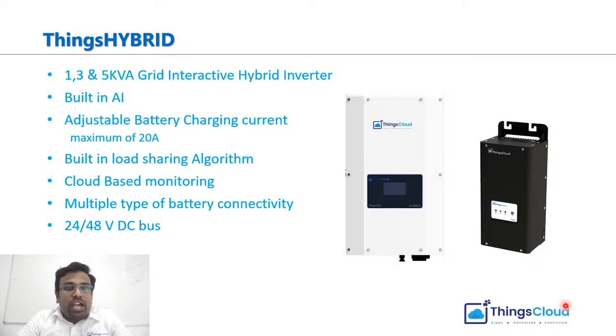And this is Things hybrid, meaning it's a hybrid grid-interactive inverter. In grid-tie systems, if there is no grid, it will not function, because grid-tie inverters take reference from the grid, and if the reference is not there, it will turn off. When it comes to hybrid, there will be a battery backup, so if there is an absence of grid, it will act as an off-grid inverter.